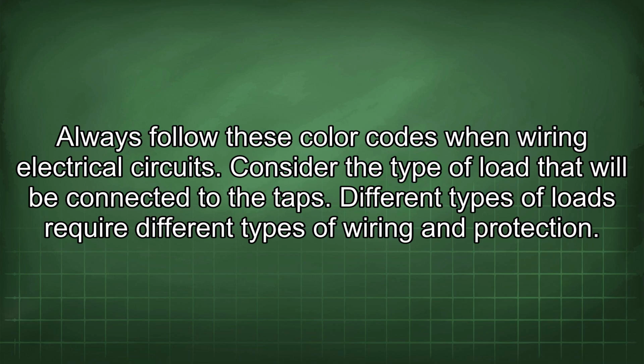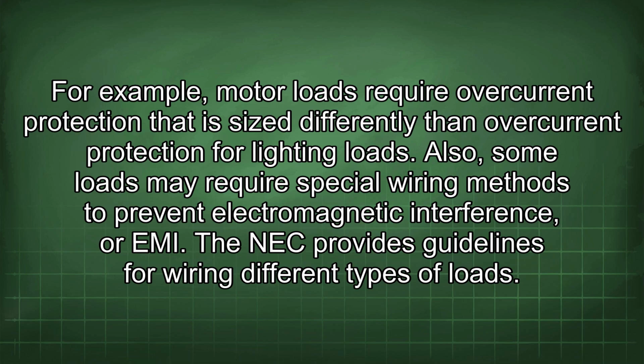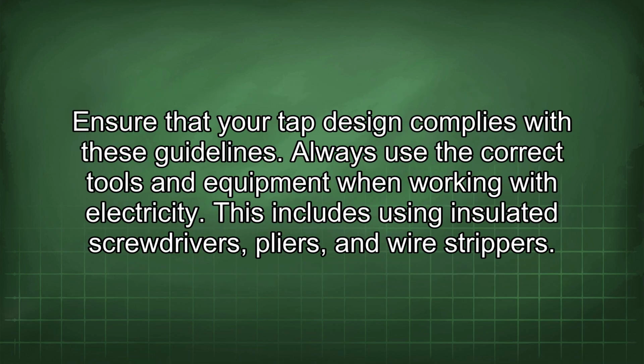Consider the type of load that will be connected to the taps. Different types of loads require different types of wiring and protection. For example, motor loads require overcurrent protection that is sized differently than overcurrent protection for lighting loads. Also, some loads may require special wiring methods to prevent electromagnetic interference, or EMI. The NEC provides guidelines for wiring different types of loads. Ensure that your tap design complies with these guidelines.